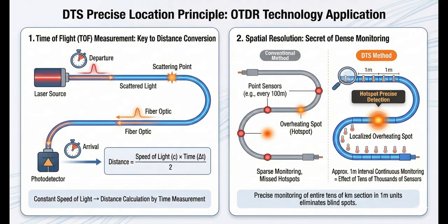Knowing temperature alone is not enough. To respond immediately, we must know where the heat is. DTS applies the OTDR principle by measuring the time of flight of the backscattered signal and converting it into distance to determine location. While conventional methods often identify only broad zones of tens of meters, DTS can pinpoint local hotspots with a fine spatial resolution of around 1 meter, significantly reducing blind spots.